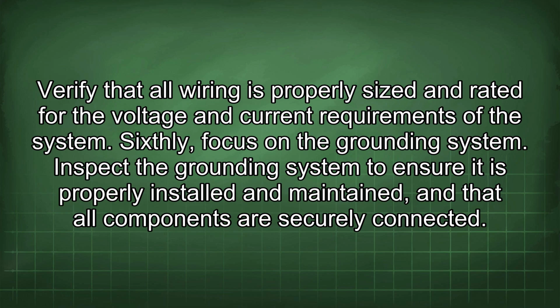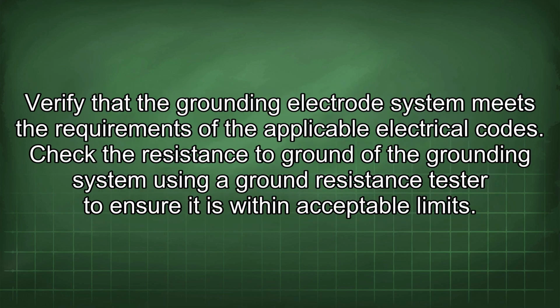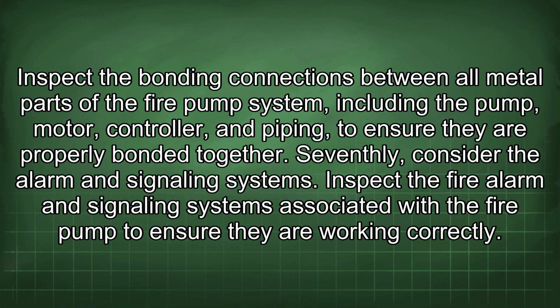Sixthly, focus on the grounding system. Inspect the grounding system to ensure it is properly installed and maintained, and that all components are securely connected. Verify that the grounding electrode system meets the requirements of the applicable electrical codes. Check the resistance to ground of the grounding system using a ground resistance tester to ensure it is within acceptable limits. Inspect the bonding connections between all metal parts of the fire pump system, including the pump, motor, controller, and piping, to ensure they are properly bonded together.